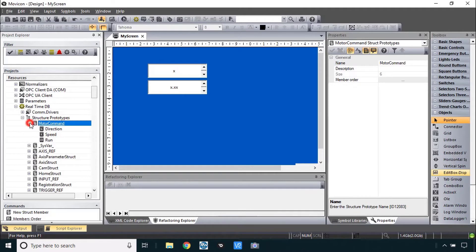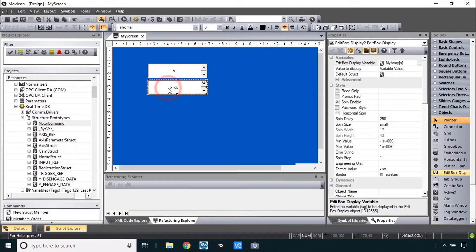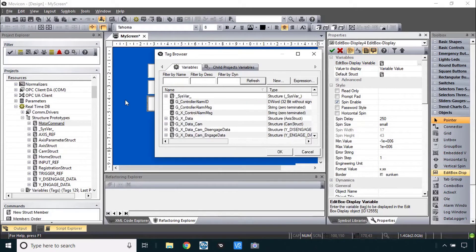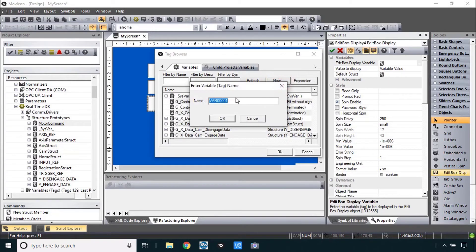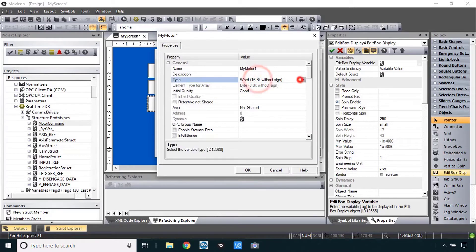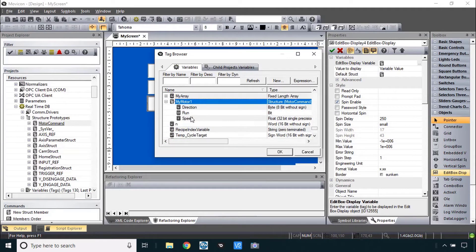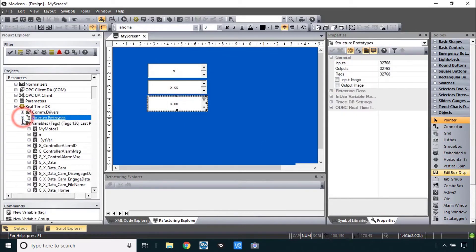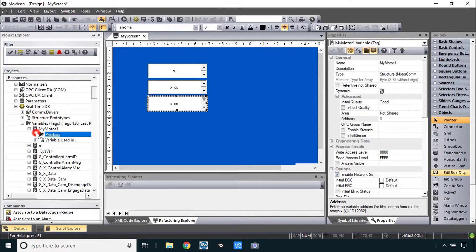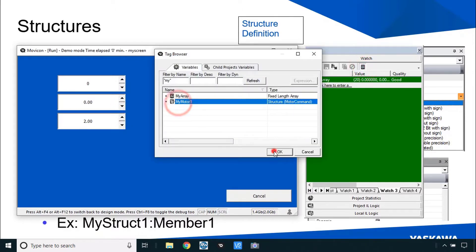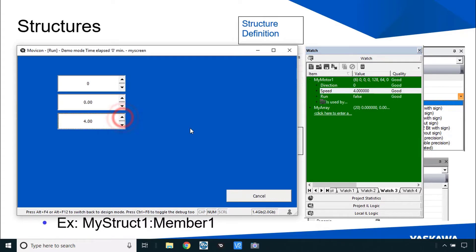That's the structure definition — in MotionWorks IEC we'd call that the data type definition. Now to create a variable, I'll go straight into an edit box display, copy one, and delete the existing variable. I'll create a variable called 'myMotor1' and change the data type definition to the structure called 'motor command'. Within this structure I'll choose the element 'speed'. I can find myMotor in the real-time DB with its different members, run this quickly, and confirm the speed value is changing.